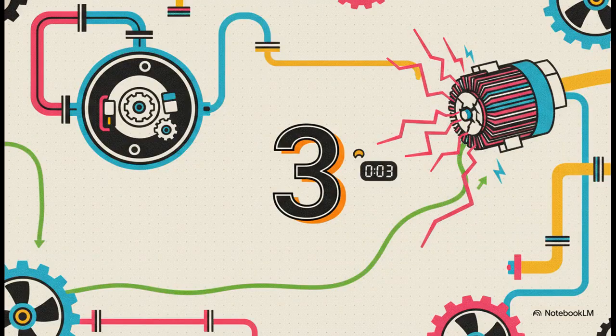And then we have the 3-minute rule. This is an absolutely crucial operational habit. Anytime your AC shuts off, whether the thermostat did it or you just had a quick power flicker, you must wait at least 3 minutes before trying to restart it. Why? Because restarting it too fast forces the compressor to push against incredibly high, unequalized refrigerant pressure. Skipping that 3-minute wait can literally cause a catastrophic compressor burnout. You'd be turning a tiny momentary inconvenience into a multi-thousand-dollar nightmare.